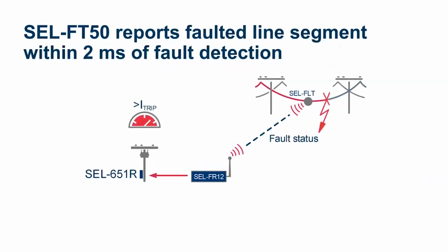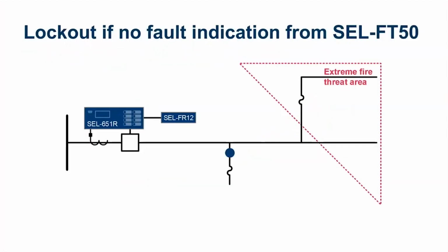If the load current is greater than 5 amps and you have a fault, then it can send the signal real quick. As I mentioned, it takes about 2 milliseconds to send the signal to the receiver, and then about 4 milliseconds for the signal to be sent to the 651R. So again, if I have a fault in the extreme fire threat area, it means my FT50 hasn't detected a fault. In that case, I'm going to directly lock out. I'm not going to reclose, I'm going to directly lock out.